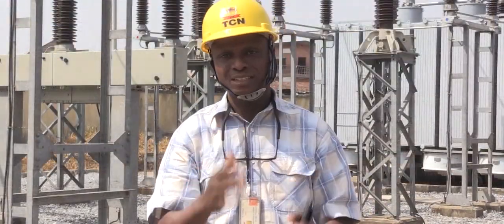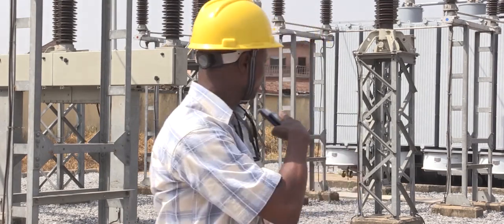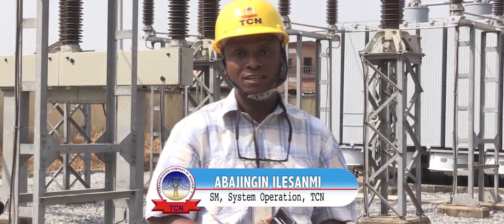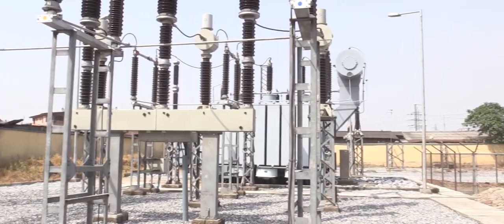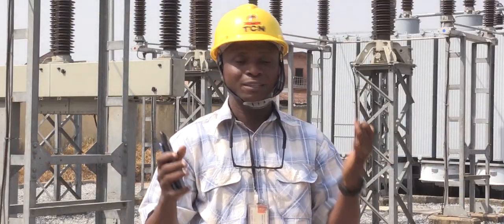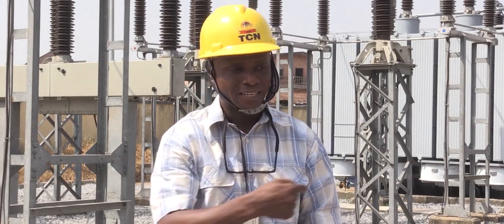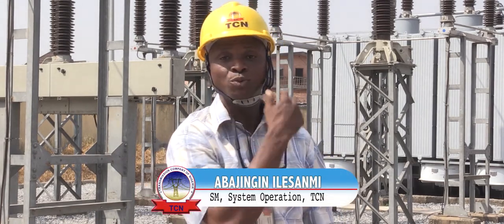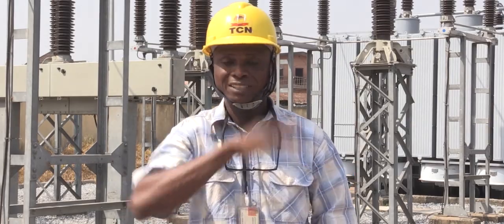The station supervisor, Engineer Ilesanmi, spoke about the completed expansion project at the Ogba substation: This one you're looking at is 100 MVA. It can carry 80 megawatts, can wheel out 80 megawatts. It was designed with three feeders, because at the moment they just have only one bay for one feeder available. So we are still expecting the distribution people to come and do the needful for them to be able to evacuate load from the transformer.